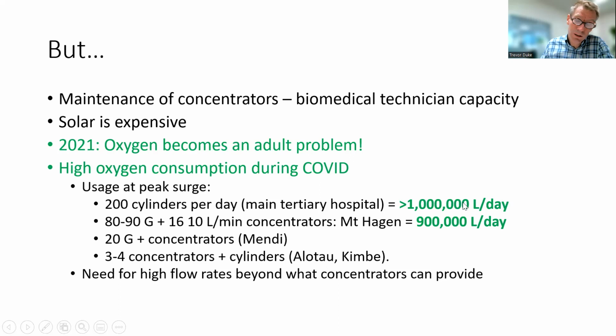This is the main tertiary hospital in Port Moresby. Even a large provincial hospital in Mount Hagen, during the 1 month of Delta surge, used 900,000 litres per day, and smaller hospitals use less, but still very substantially more than they had before. This is, of course, for adults and children, as were the calculations that I made in 2012. Part of the reason for this was that there was a need for much higher flow rates beyond what concentrators can provide.